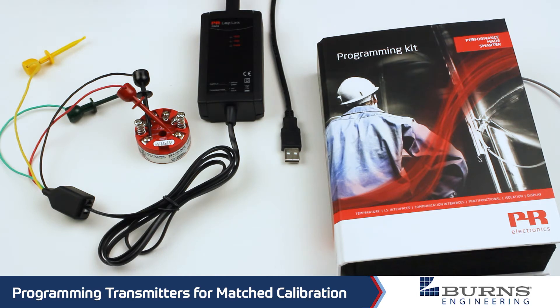So when we match the PRT to this transmitter and include some other minor error sources, we end up with about plus or minus 0.2 degrees C for system accuracy over quite a wide temperature range — certainly 0 to 200 degrees C, we're easily within that plus or minus 0.2 degrees C tolerance band. Now we'll jump over to the software and I can show you how to plug in all those coefficients and upload them into the transmitter.